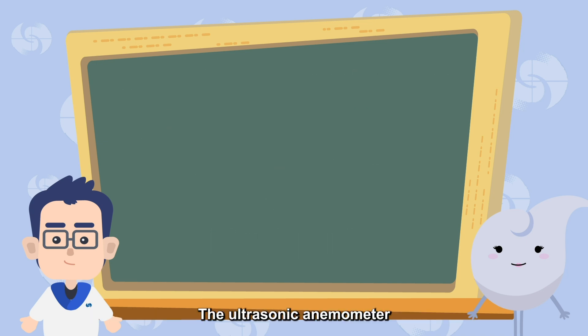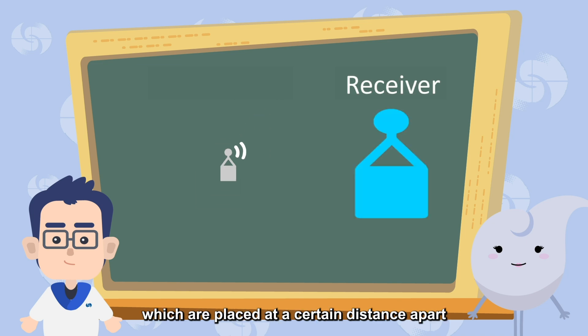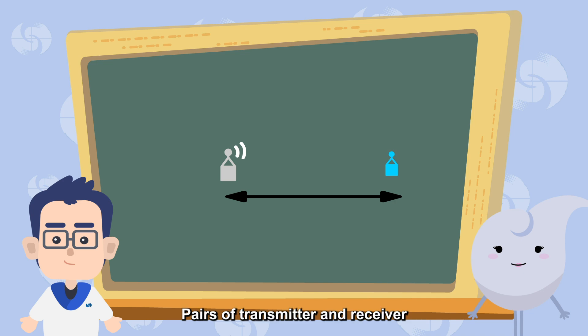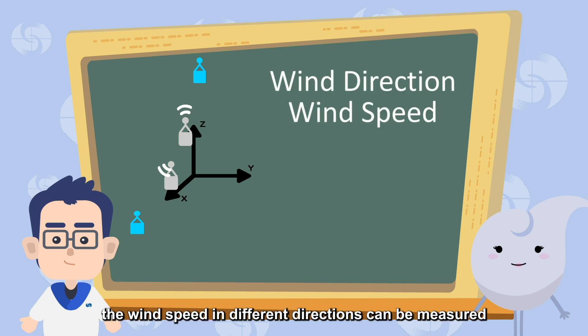The ultrasonic anemometer has signal transmitter and receiver, which are placed at a certain distance apart. Pairs of transmitter and receiver will be placed in different directions. In this way, the wind speed in different directions can be measured, so as to obtain the direction and speed of the wind.